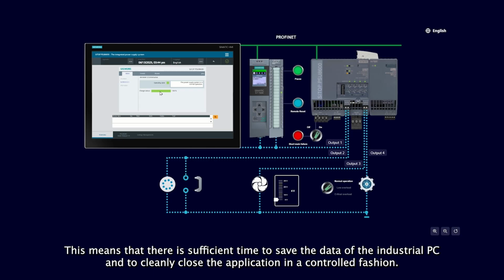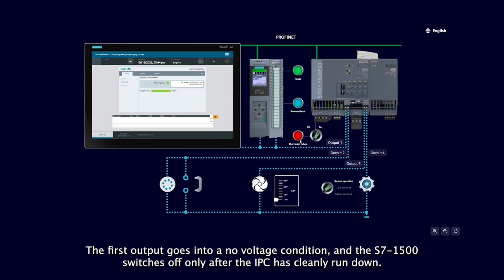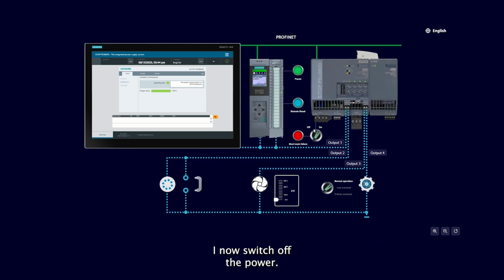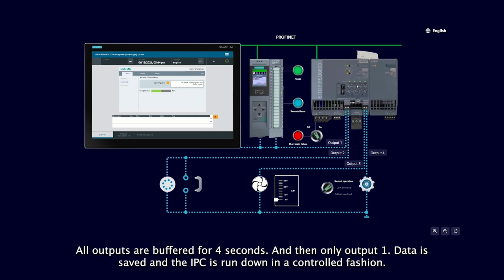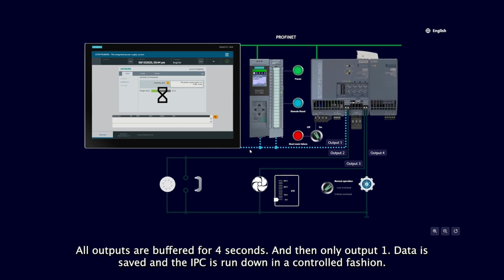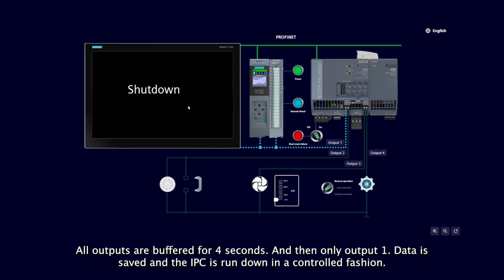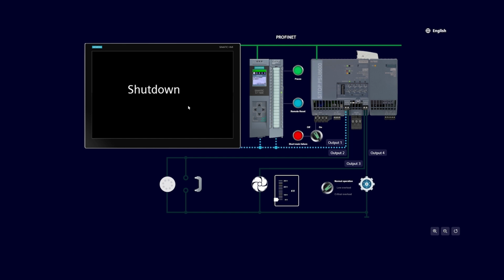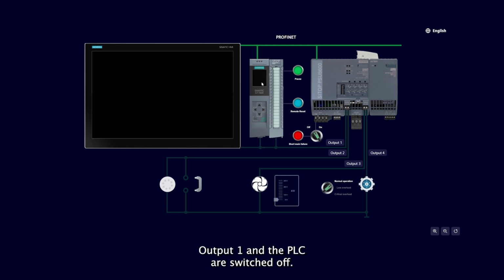This means that there is sufficient time to save the data of the industrial PC and to cleanly close the application in a controlled fashion. The first output goes into a no voltage condition and the S7-1500 switches off only after the IPC has cleanly run down. I now switch off the power. All outputs are buffered for 4 seconds and then only output 1. Data is saved and the IPC is run down in a controlled fashion. Output 1 and the PLC are switched off. The application has been correctly terminated.